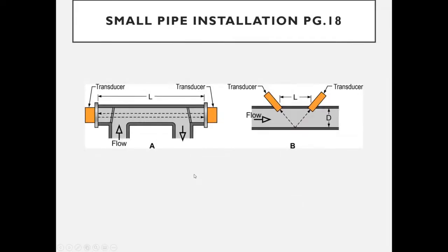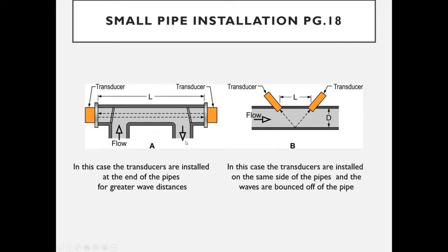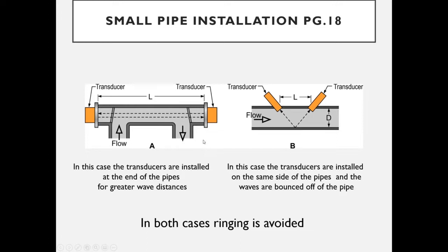Revisiting small pipe installations: the configuration with transducers on the same side bounces the ultrasonic wave off the back pipe wall. An alternative is using a fast-loop bypass with transducers on opposite sides, where the loop width can be adjusted to provide sufficient travel distance for the electronics. Both approaches avoid the ringing problem that occurs when the pipe diameter is too small.